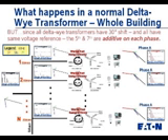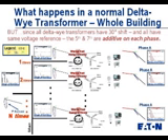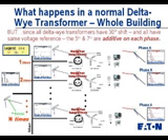What's interesting to note is what occurs on the primary side of those transformers. On the individual phases — the phase A's of each of these different legs — the fifth and seventh have a tendency to be additive. So the phase A of one branch and the phase A of another branch: fifth and seventh are in phase with each other and are additive from each of the sub-panels. We're able to see a large fifth and seventh component on the switchgear and main service, multiplied by the number of sub-panels.